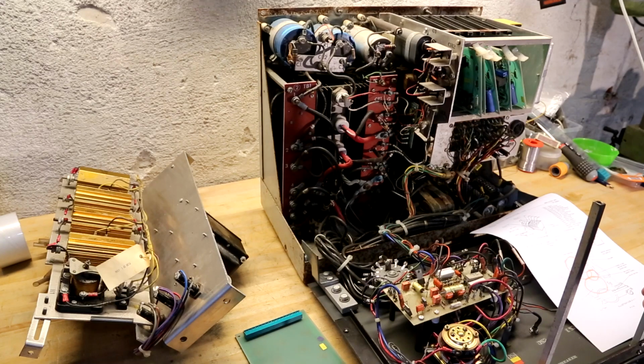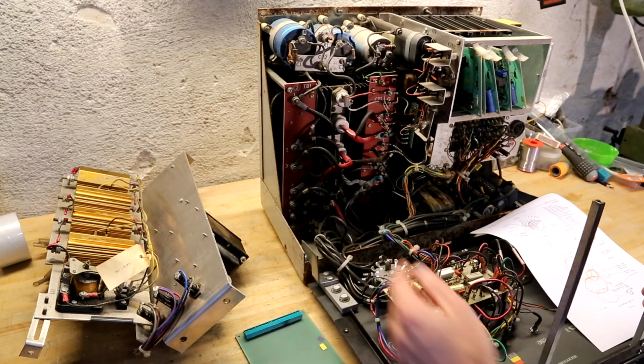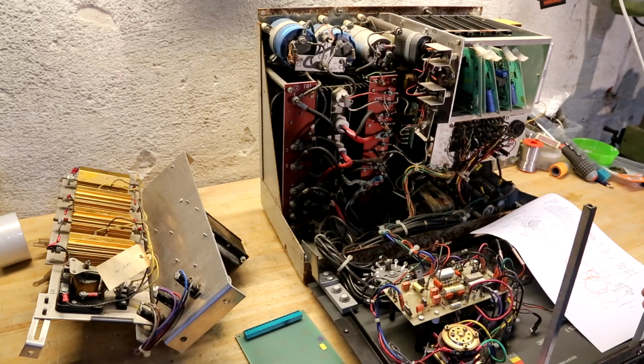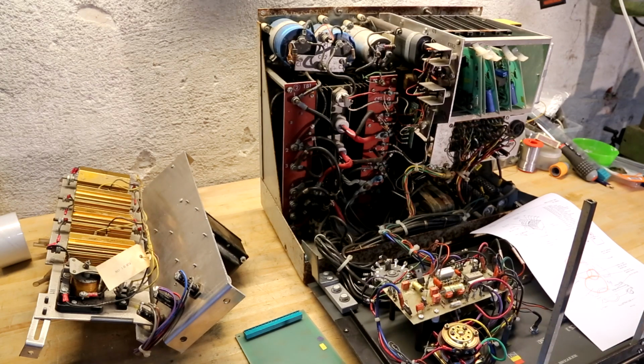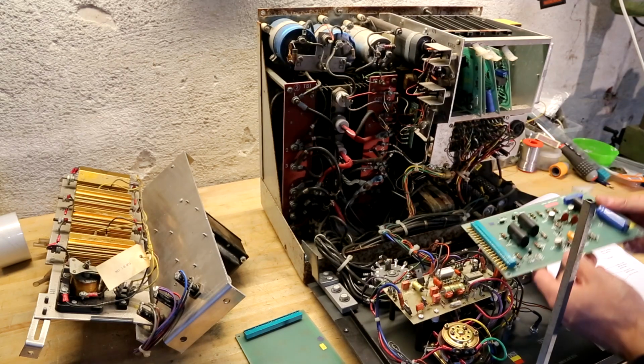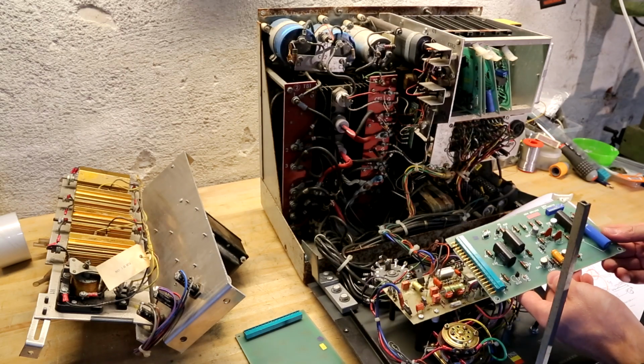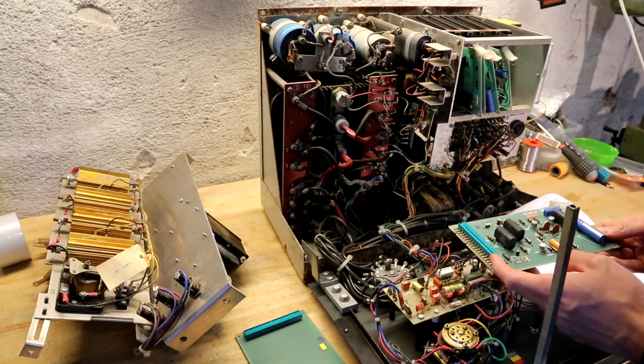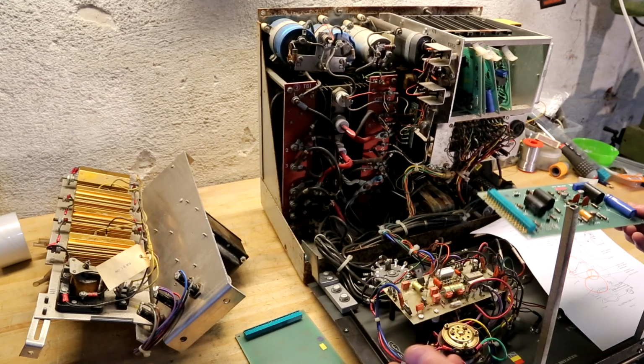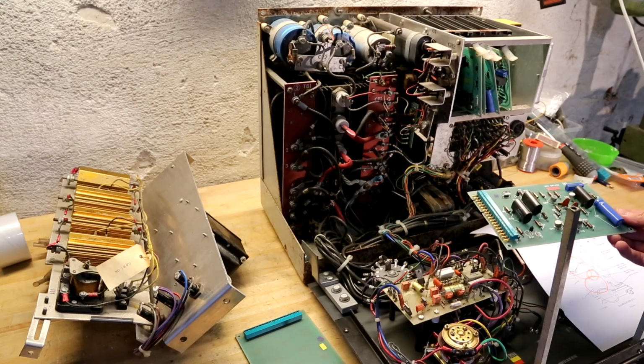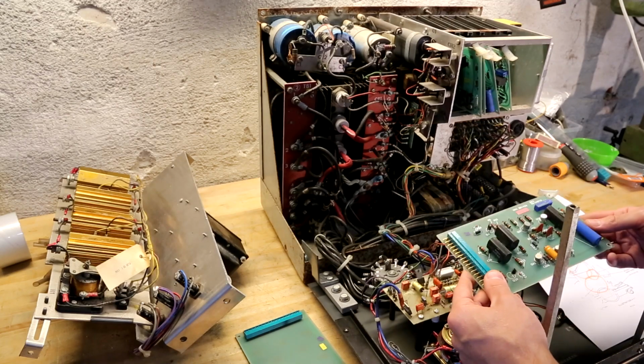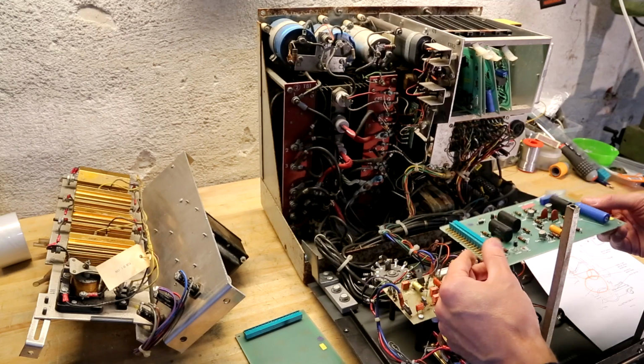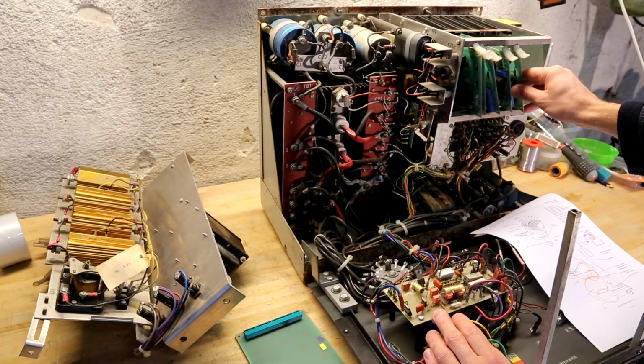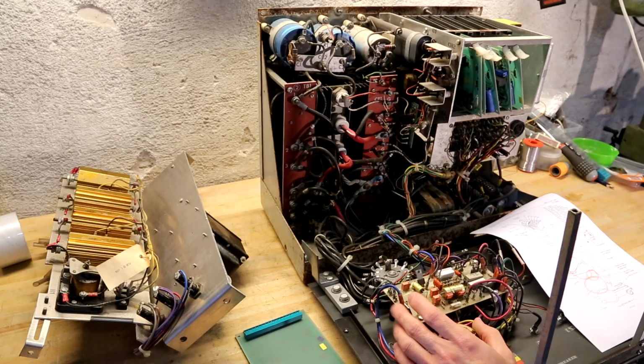Other than that, over here there are two inverters in this. There is a 60 Hertz inverter, which is quite fun, because that's card 5. That's not the pulse board. That would be 3A6. This is 3A5. This is the 60 Hertz inverter pulse board. Since this is a battery-driven unit, but it comes from America, which is a 120 volt country, they have a built-in 60 Hertz inverter to generate an AC voltage according to what would be at the mains supply in the US. So 2 of these SCRs are actually the 60 Hertz mains inverter, and another 2 or 4 are the big X-ray inverter drivers.